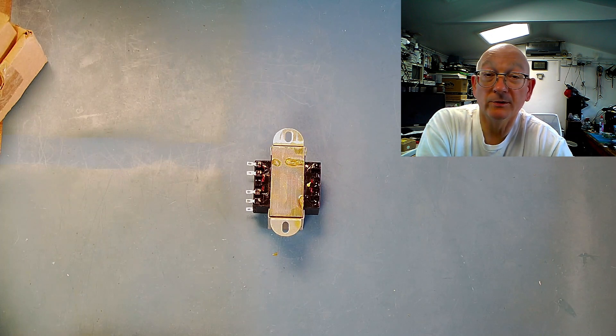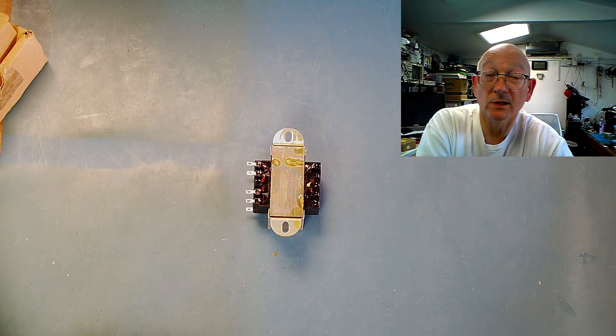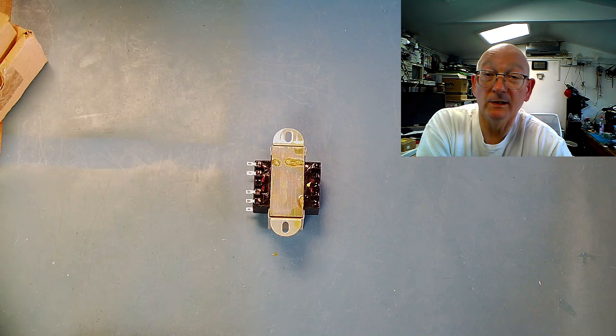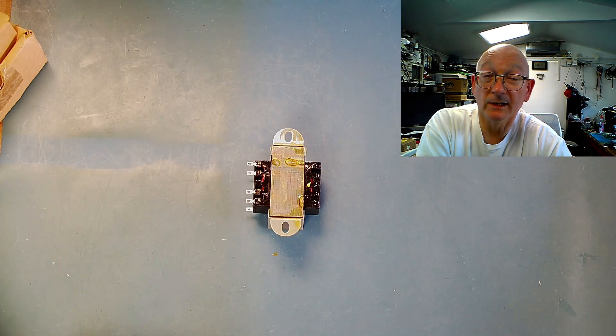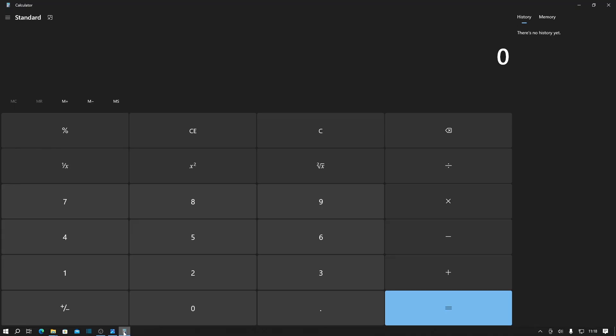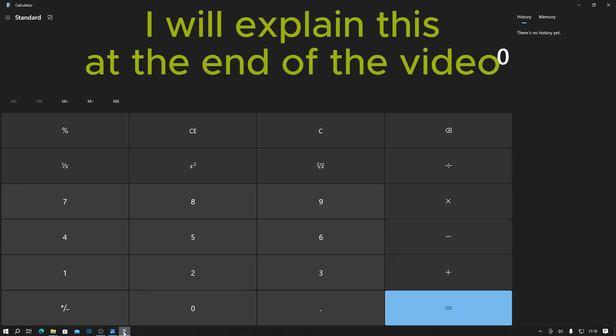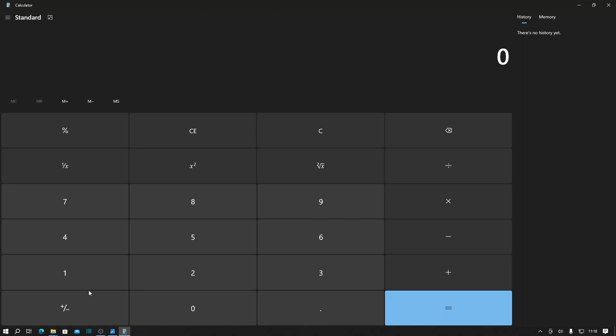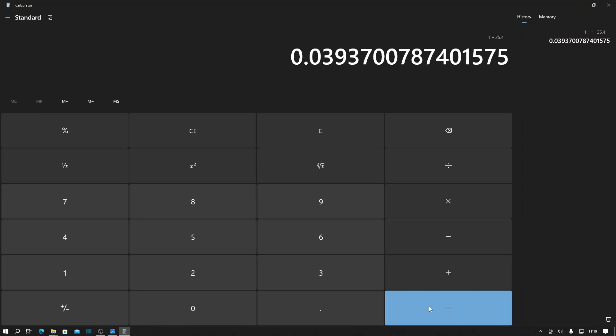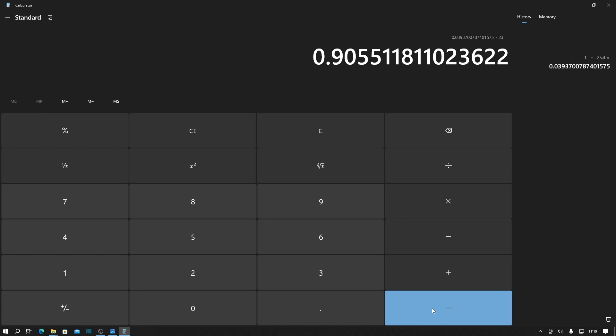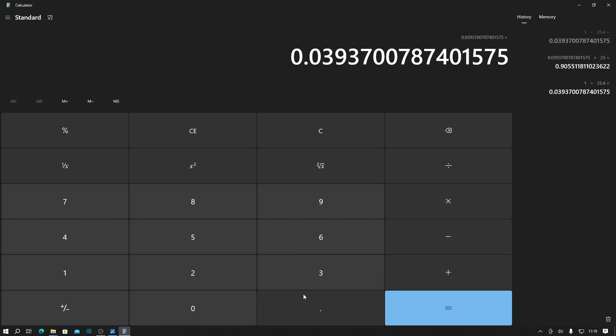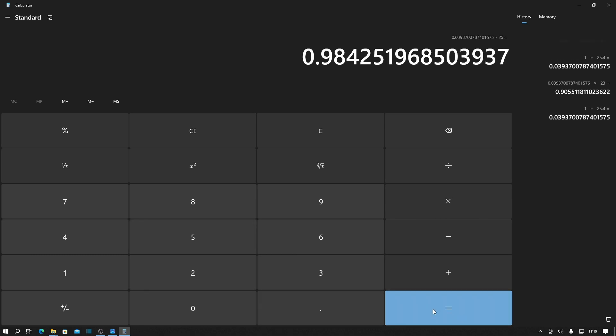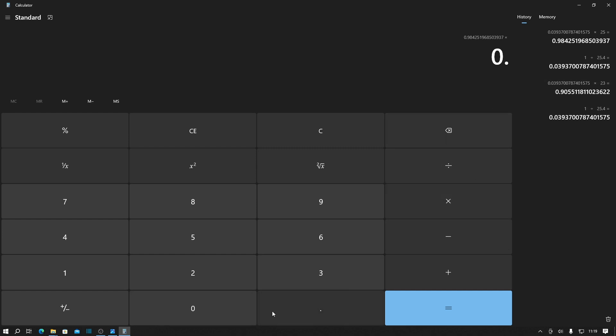We'll go through the example with this transformer and I'll show you on the calculator app the stages we need to go through to calculate VA rating, and then at the end I'll show you the formula that I use. We need to convert our dimensions in millimeters into an inch size. I think the easiest way to do that is to say one inch and then we divide that by 25.4 which is the number of millimeters in one inch, and then we'll multiply that by 23 which is our first dimension. Then we can do the same, so 1 divided by 25.4 equals, then we multiply that by 25 which is our second dimension in millimeters.